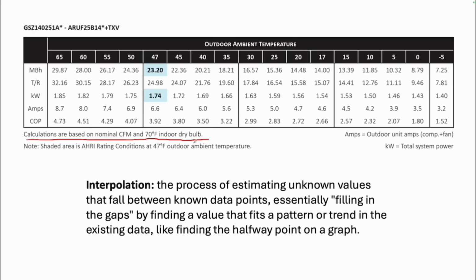Now, just for the sake of brevity, I didn't bring in the cooling capacities, but when you find this document, and I'll tell you what I typed in: Goodman GSZ 14 heating capacities, or sometimes you may put in submittal data. Different manufacturers call it different things. Carrier lists their capacities in what they call their product data. York lists them in what they call their technical guide. So you just have to figure out the wording to get the right results. You may have to try a few times, but again, it's not too hard to find. Now, nominal CFM in this particular unit, I happen to know, is 435 CFM a ton, not 400.